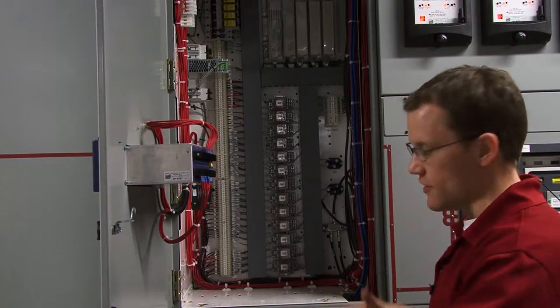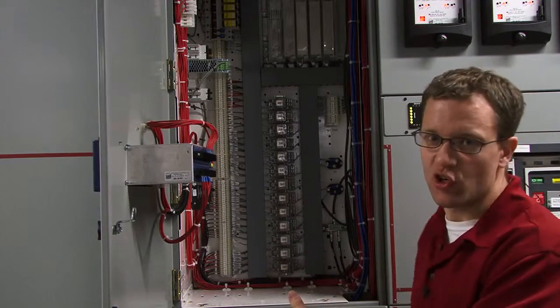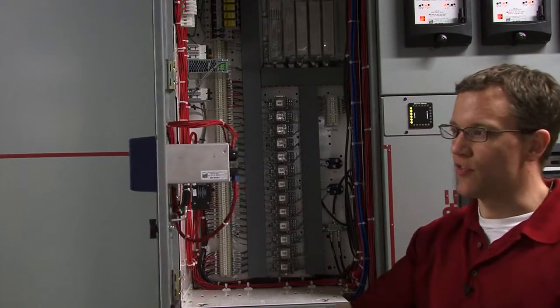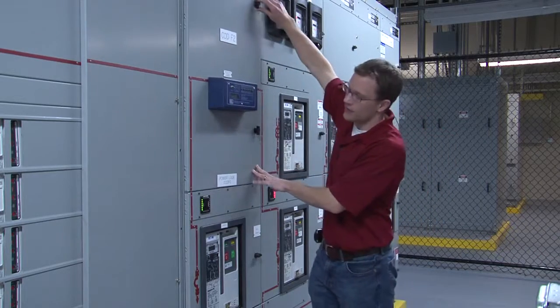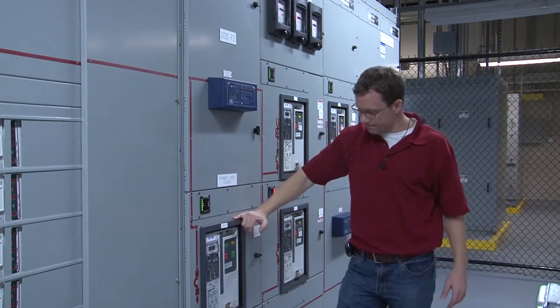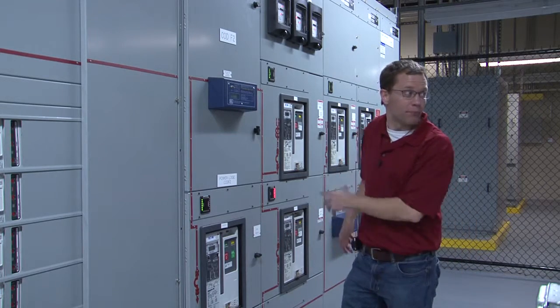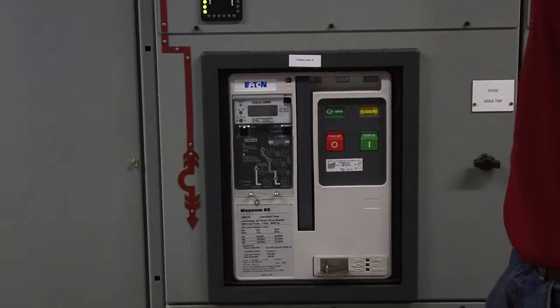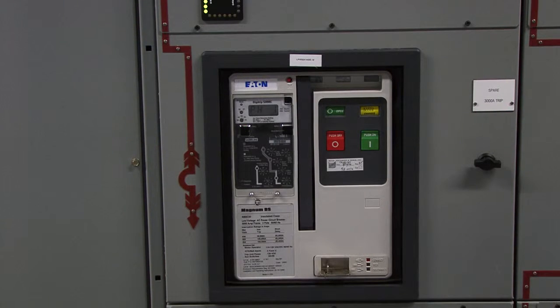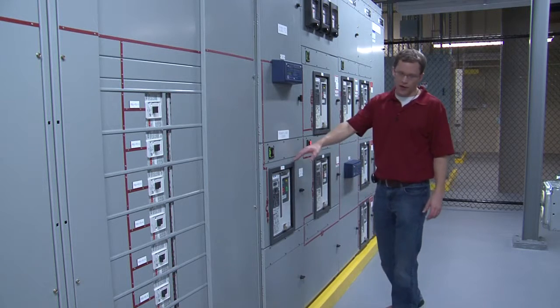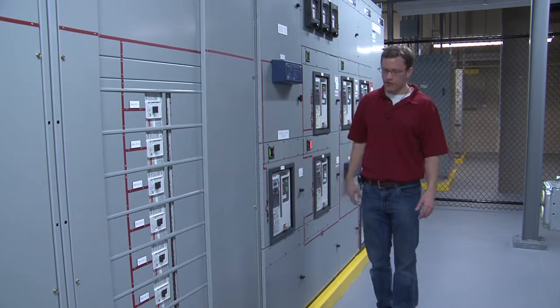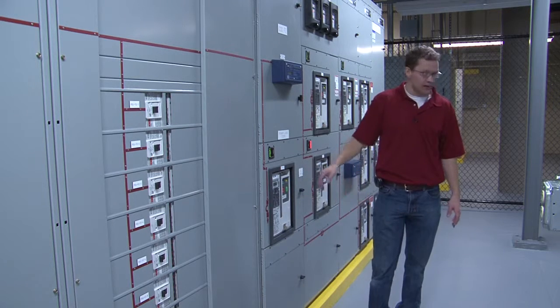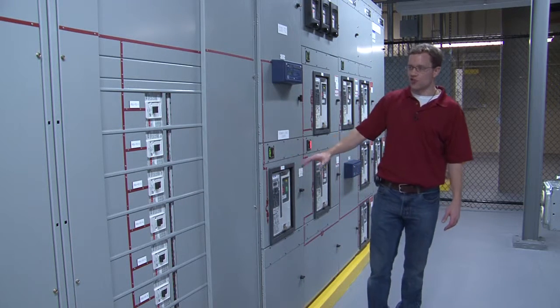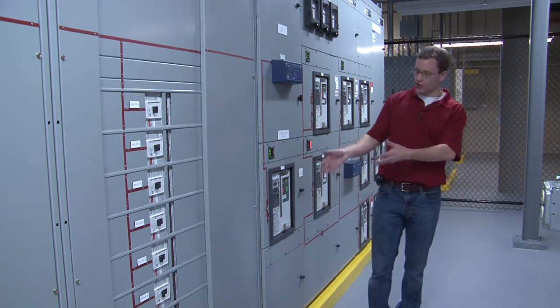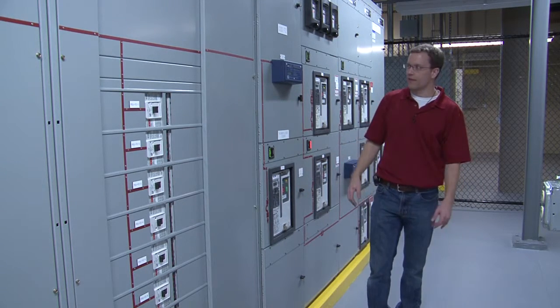In phase one, there is no Square D cubicle located in each COD. In this phase there is. And then this is just a spare breaker that they could pull out and plug into one of the other cubicles. It's a 3000 amp breaker, and it's supposed to be set up the same as these two. So normally this breaker is open. It's monitored by Convergent, but it doesn't feed anything, and it's normally open. So they could either choose to use it as a replacement breaker, or they could add a future feeder out of here to someplace else.